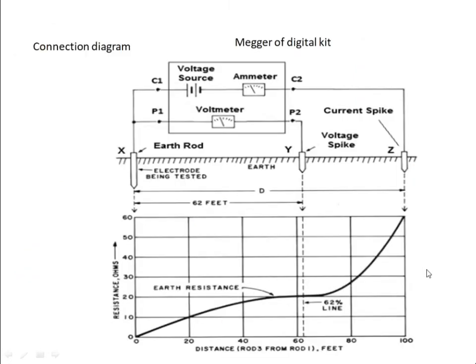So let us come back to the schematic diagram. After the schematic diagram, we are going to see the connection diagram. Try to understand the connection diagram. The electrode Y is the voltage rod, Z is the current rod. The graph shows the variation in the resistance when distance changes. 3 sets of readings are taken by shifting the voltage rod to 3 different places. The first position is 60 feet away from the main rod. The second position is 10 feet farther from the first position, and the third position is 10 feet closer to the main rod. The voltage spike rod, the center rod shown in the figure, is placed at various distances, and 3 different readings are taken.